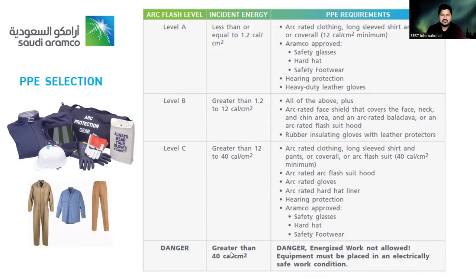Danger zone, the critically terrible danger zone, is greater than 40 calories per square centimeter. So danger: energized work not allowed. Equipment must be placed in an electrically safe condition. Okay, so this slide is also very important. You can take a screenshot, and as I always request, don't move on to the next slide until you understand it all the way, 360 degrees.